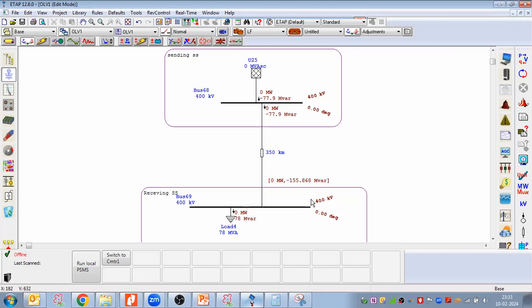See, if you are getting the 400 kV regulated voltage, no reactor is required. But if I'm not able to maintain my bus voltage, and it's jumping to 430 kV, due to that reason I put the reactor.